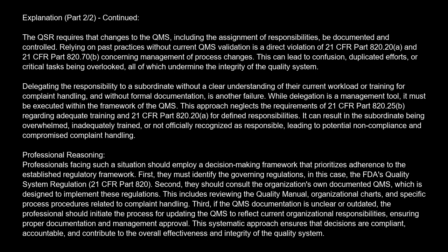This approach neglects the requirements of 21 CFR Part 820.25(b), regarding adequate training, and 21 CFR Part 820.20(a) for defined responsibilities. It can result in the subordinate being overwhelmed, inadequately trained, or not officially recognized as responsible, leading to potential noncompliance and compromised complaint handling.